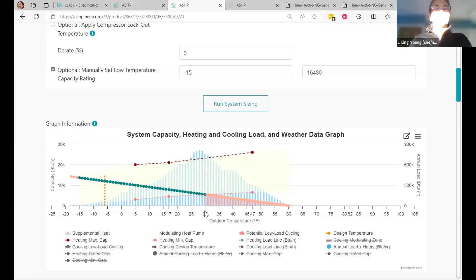So what I'm seeing is I chose a smaller heat pump, but it's still got this wedge down here where I'd expect the heat pump isn't performing very well. In fact, at 32 degrees is where these two lines cross and the heat pump can start modulating, and for this one it's 30 degrees—hardly any difference at all. So it turns out we really need an even smaller one.